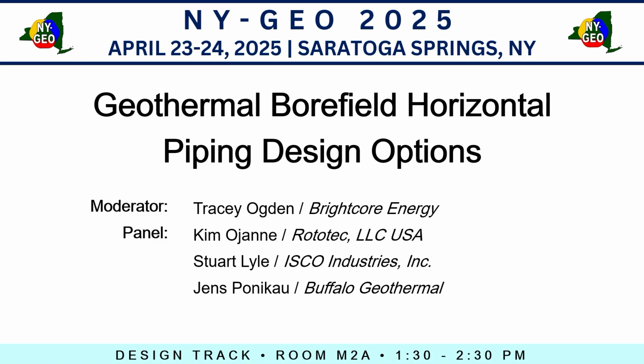Just by nature, how they're designed, they have a very high pressure drop. And I don't want that in there. I'd rather have a little unbalanced loop field. And we're talking about, again, not even a 1% difference between the furthest and the closest loop. I don't see a need for it.